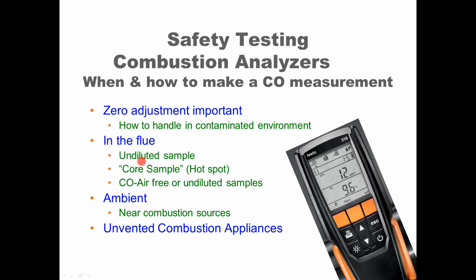You want to be measuring the core sample, which is a repeatable area. It's also called the hot spot. It's where most of the flue gases are moving up through the stack. You use the thermocouple probe, the temperature probe, to find that core area. That gives you a more repeatable measurement.